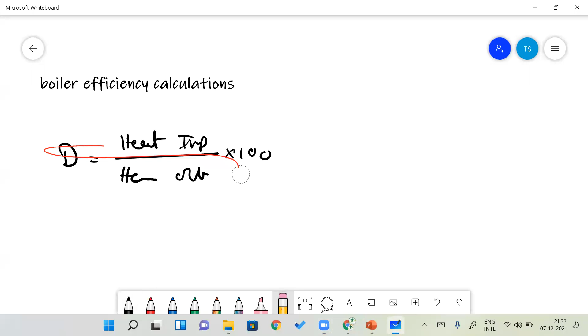When you're talking about the direct method, you should know things like the quantity of steam generated. How much steam is generated is very important, because based on that you have to find out how much heat output was generated. The quantity of fuel consumed and the quantity of steam generated are needed. The working pressure of the steam is also required, as are the temperature and pressure, in order to find out how much heat the steam contains, that is, its enthalpy. The type of steam generated, whether saturated, superheated, or wet steam, is also important. And the temperature of the feed water. What is the feed water temperature?